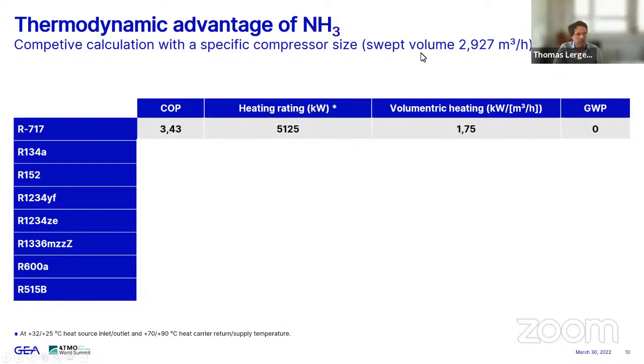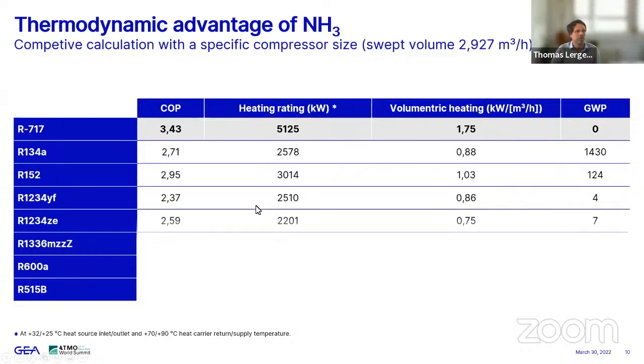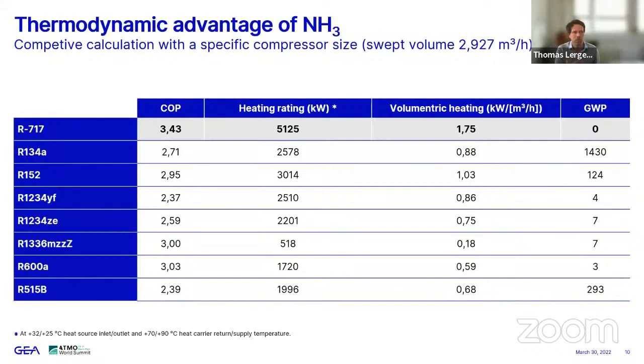This calculation is based on this compressor size and a heat source inlet and outlet of 32 to 25. So basically you're using ambient temperature heat sources, and you're looking to supply heating consumers with a return and supply temperature of 70 to 90 degrees Celsius. These are the parameters that form the basis of this calculation. If we do exactly the same calculation for the different refrigerants, we see a lot of different numbers, and there's no need to go through all of them. But it's quickly seen that ammonia in this application range clearly provides the best efficiency, the best COP, and the highest rating, the highest capacity. Basically, you can get more out of ammonia than with the other refrigerants.